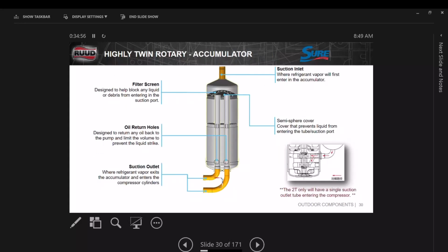On the side of the compressor, you notice we have an accumulator. This is to recover the oil back to the unit and take any liquid that may be in the suction gas to keep it from getting into the compressor. Because just like a scroll compressor or any compressor, we're not supposed to have any liquid at all in the suction line. The top of this container, as you can see, has a semi-sphere up here, a little cover plate and a screen that goes over the top of the two pipes. That's to keep the liquid and oil from going directly into these pipes.